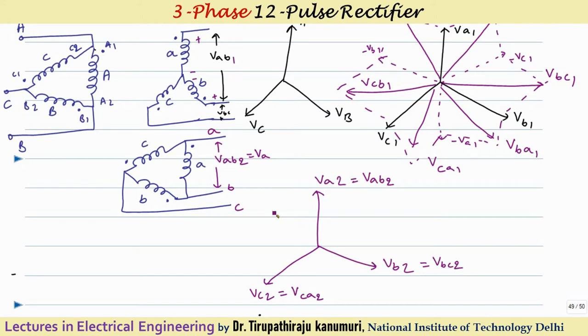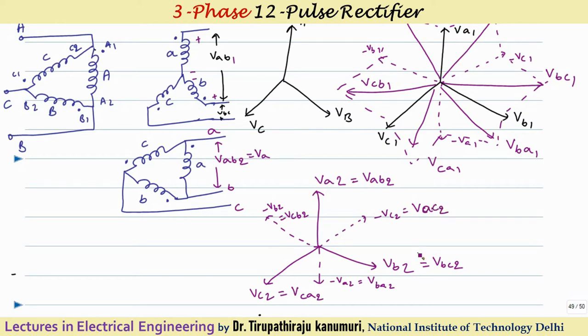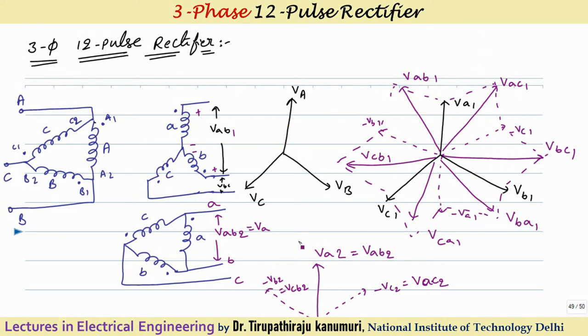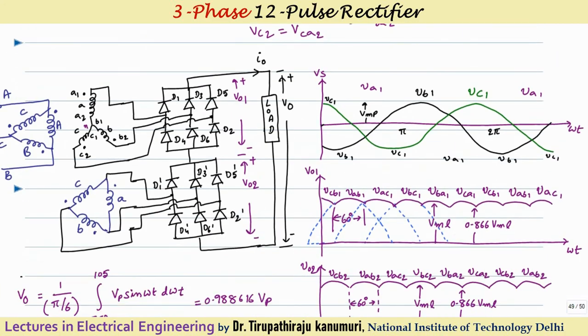Comparing the line voltages of the two secondaries, VAB2 is vertical, aligning with VA1, but VAB1 is leading by 30 degrees. That means, with respect to the line voltages of these two secondaries, they are displaced from each other by 30 degrees. We are going to use this analysis to analyze the 12-pulse rectifier.